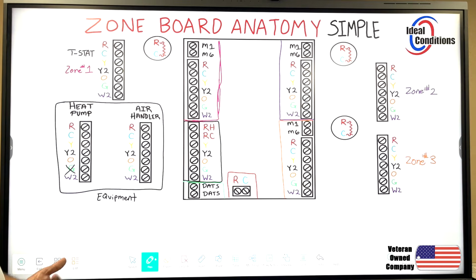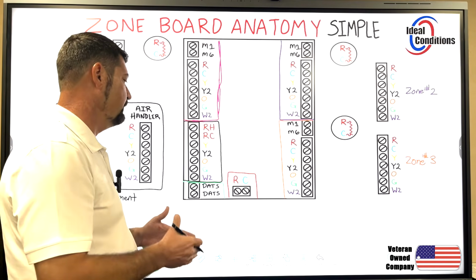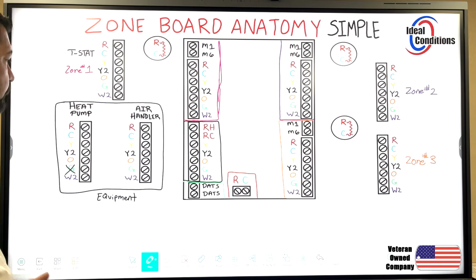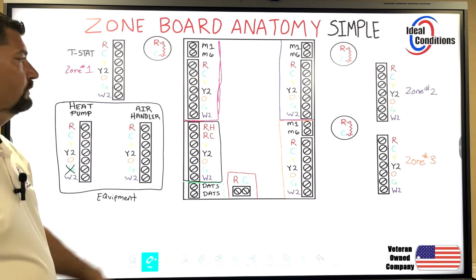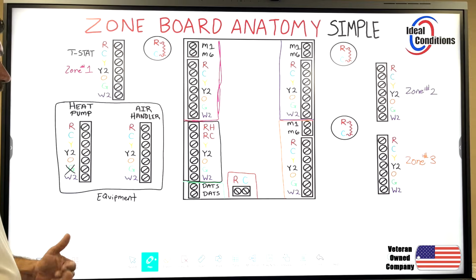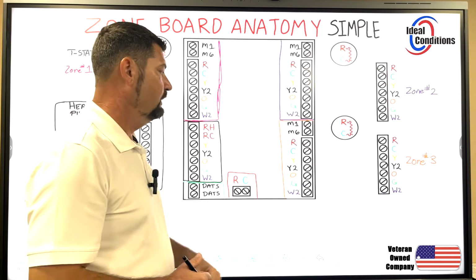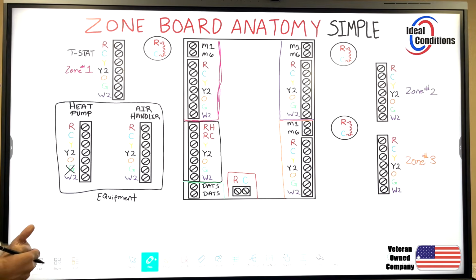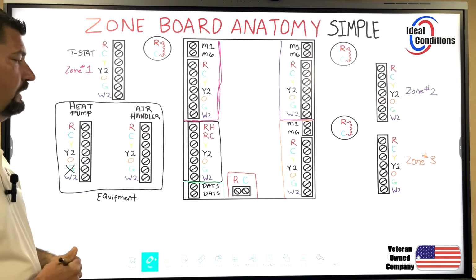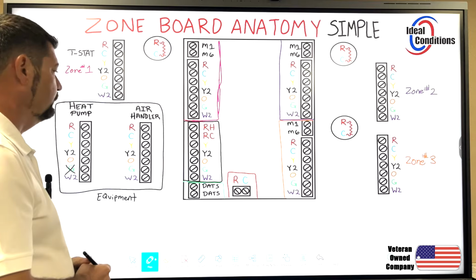So I told you I was going to talk about 2 different types of transformers, primary and secondary, and how to wire that up. In the last video I didn't really cover the primary transformer wiring, I covered it vaguely and mostly spoke about the secondary transformer. I'm going to do it both ways here, because you can take the primary 40 VA transformer out and put in a primary 75 VA transformer, primary meaning there's only one transformer servicing the equipment and the zone board. So if we step that volt amps up to 75 VA, we can carry the load of these dampers and energize these thermostats without causing a voltage drop, which would increase the amp draw and create problems, right? We don't want that.